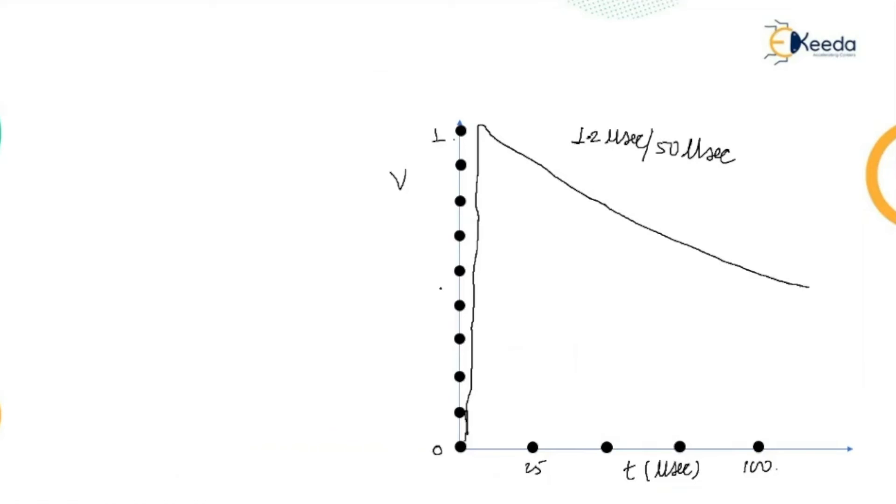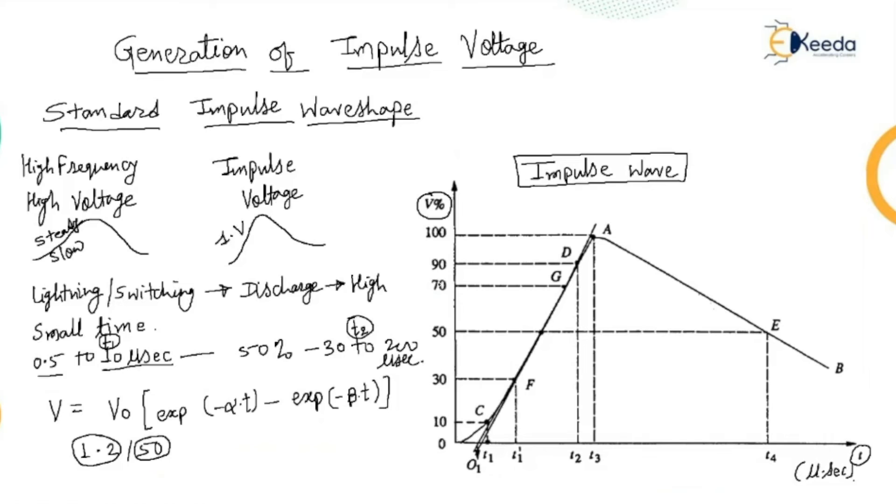So, referring to this waveshape, the peak value is reached. Peak value A is fixed and referred to as 100% value. The points corresponding to 10% and 90%, so 10% and 90% of the peak values are located in the front portion, points C and D. So, this is points C and D. The line joining these points is extended to cut the time axis at O1. That cuts the point at O1. So, O1 is taken as the virtual origin. O1 is taken as the virtual origin. So you can see here that the virtual origin is shown here.